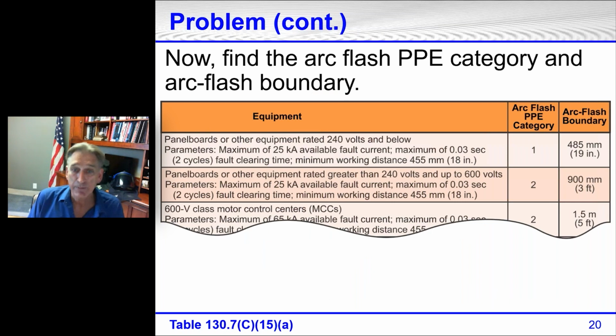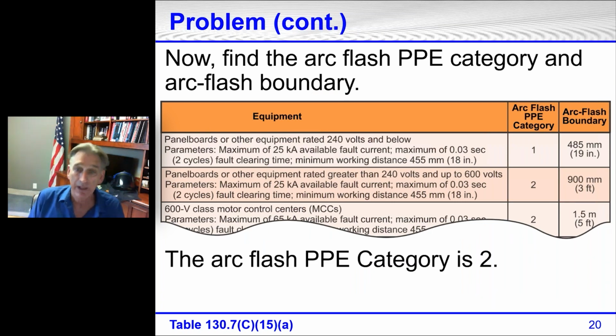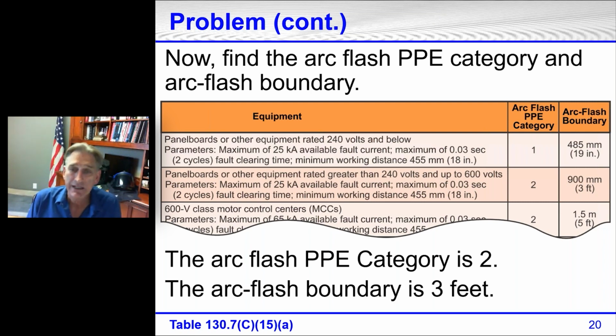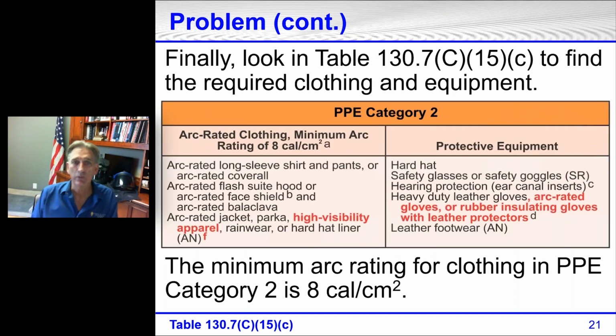Now we find the arc flash PPE category. It is category 2, arc flash PPE category 2. Then we find the arc flash boundary, go a little bit further. It is 3 feet. Finally, we look at table 130.7C15C to find the required clothing and equipment. Category 2 is what we have to have. So we look at PPE Category 2. This is mostly the same as what we looked at with Category 1, except the minimum arc rating of Category 2 is 8.